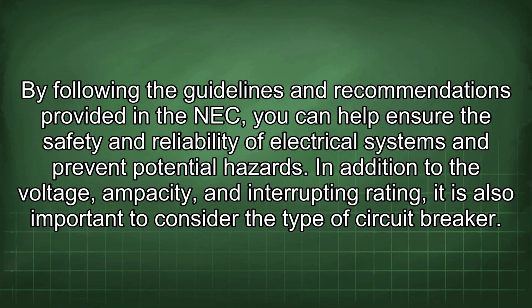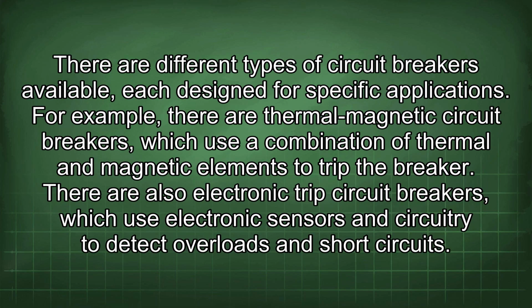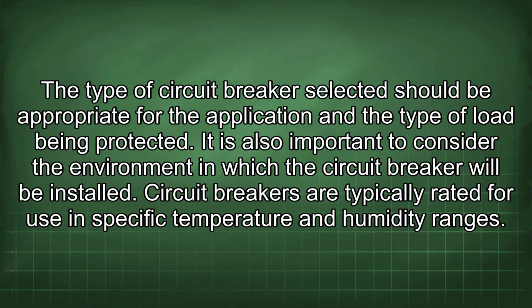In addition to the voltage, ampacity, and interrupting rating, it is also important to consider the type of circuit breaker. There are different types of circuit breakers available, each designed for specific applications. For example, there are thermal magnetic circuit breakers, which use a combination of thermal and magnetic elements to trip the breaker. There are also electronic trip circuit breakers, which use electronic sensors and circuitry to detect overloads and short circuits. The type of circuit breaker selected should be appropriate for the application and the type of load being protected.